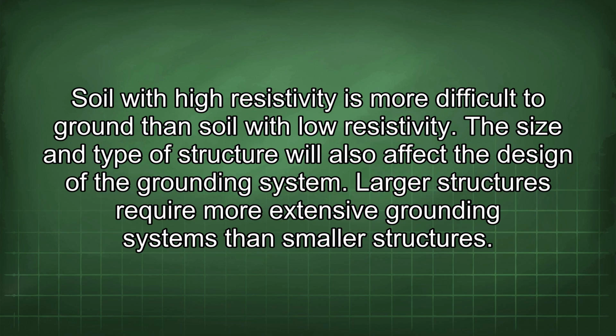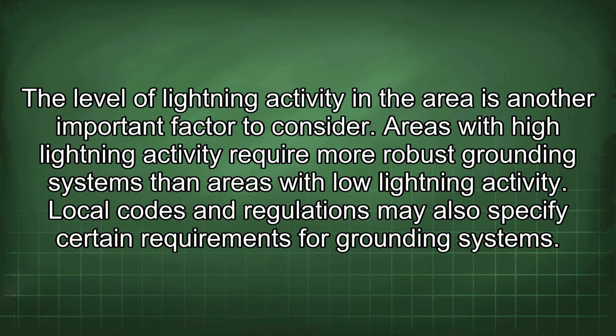Soil with high resistivity is more difficult to ground than soil with low resistivity. The size and type of structure will also affect the design of the grounding system. Larger structures require more extensive grounding systems than smaller structures. The level of lightning activity in the area is another important factor to consider. Areas with high lightning activity require more robust grounding systems than areas with low lightning activity. Local codes and regulations may also specify certain requirements for grounding systems.